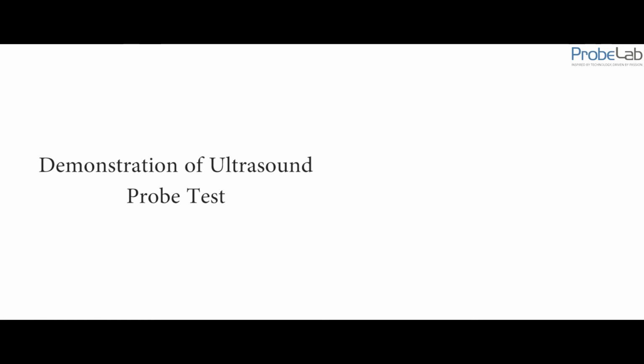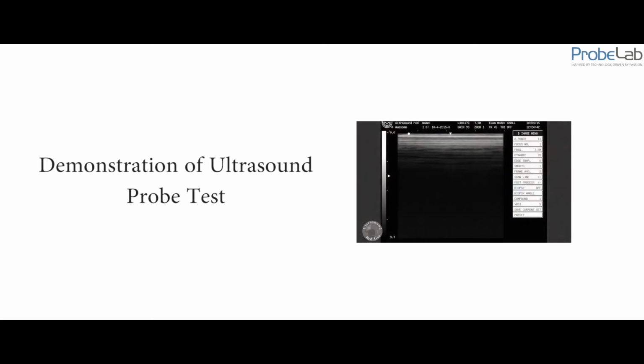I'm going to go ahead and turn the gain up so I can see ring down. I'm going to check for errors with the lens in the far field. I'm going to then take my key and gently place it on, again with the flat end only, not a jagged key. I'm going to go ahead and start from one side and observe the ring down. And I'm looking for any kind of shadowing. Shadowing could indicate a weak element or a faulty element. And as I see, this probe is in pretty good shape.